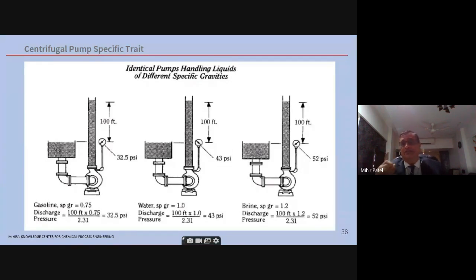Number one, your discharge pressure will be higher. So is your discharge piping suitable for that? Number two, the power drawn by the pump will be higher, so your motor should not trip. The impeller will still try to build 100 feet. So this is an important thing one should remember for brownfield jobs.